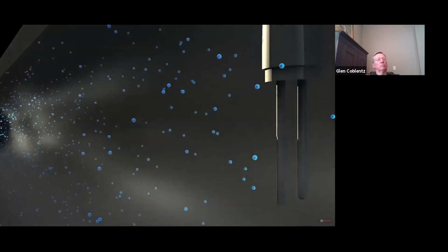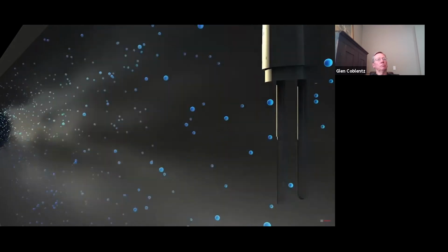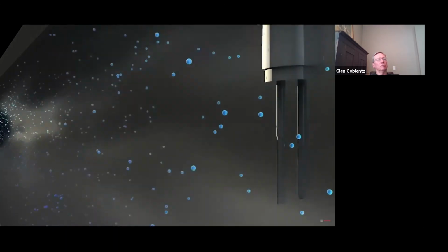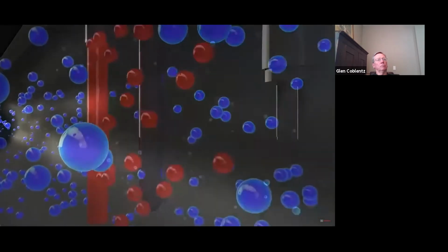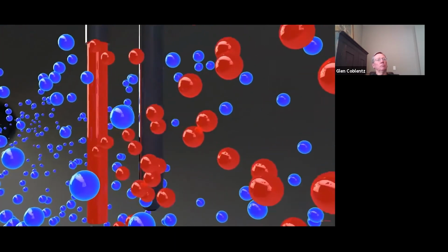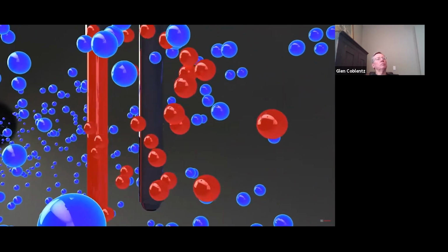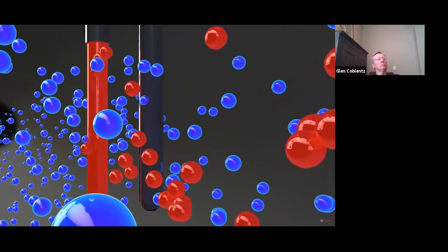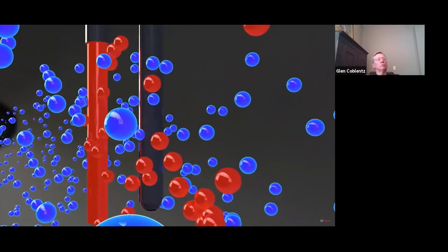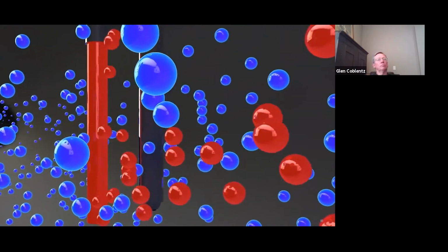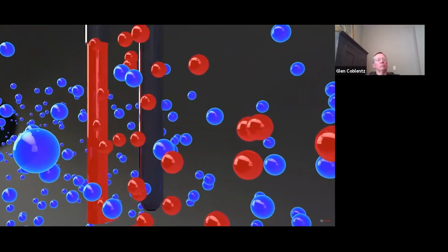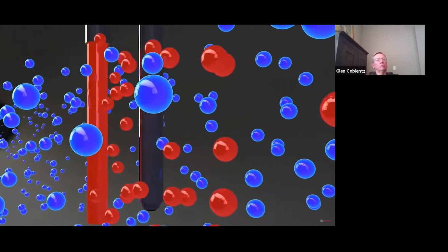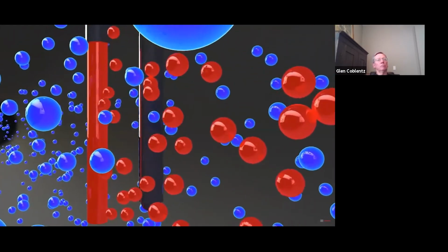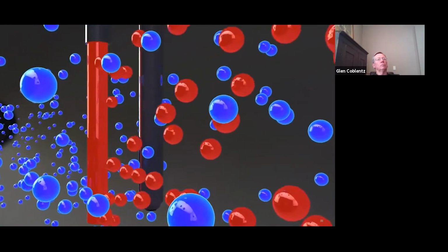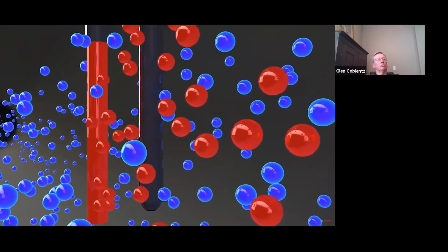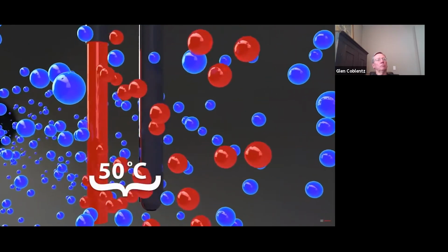As soon as the fluid flow begins, heat is drawn from the heated velocity sensor via the gas molecules flowing past. The heat is dispersed as it is carried off by the flow. To really visualize what is going on from a molecule's perspective, let's slow everything down and zoom in. Each gas molecule flowing past the heated velocity sensor has an important job to do. As the gas molecule flows past the sensor, it heats up and carries this heat away with it downstream. The corresponding cooling effect is measured and compensated for instantaneously by the instrument's sensor drive electronics, which instantly add more heating current to the sensor to maintain that constant temperature differential of 50 degrees Celsius.